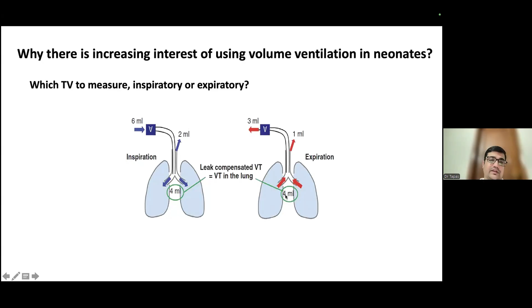As the amount of leak increases, this relation also goes off. Here you can see that the endotracheal tube leak is almost 50%. 6 ml is going in and 3 ml is coming out, so almost 50% leak is happening through the endotracheal tube. As the amount of leak increases, this correlation will go off, and as the amount of leak decreases, this correlation will actually increase. So the expiratory tidal volume is the one that closely matches with the tidal volume that is going inside the baby's lung.